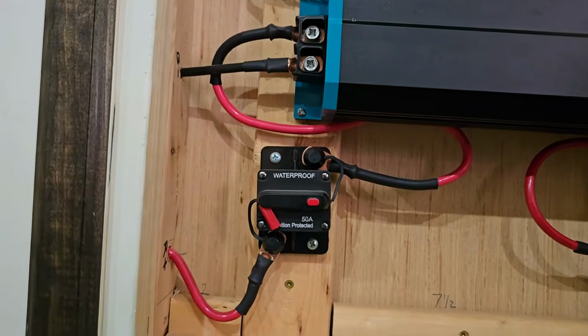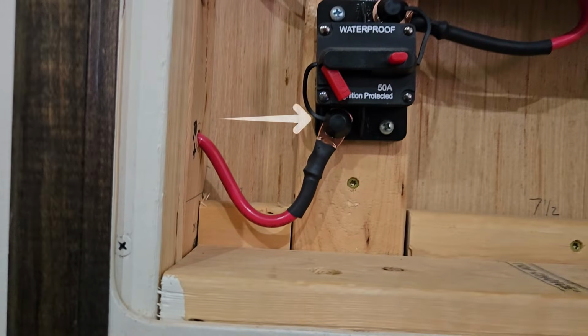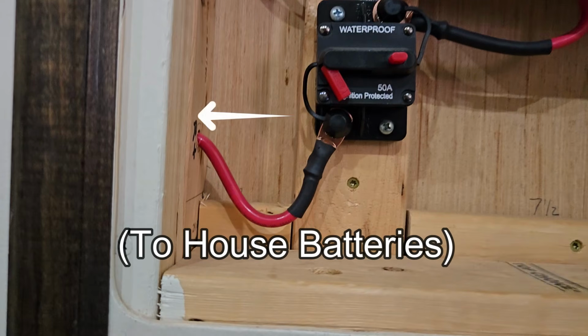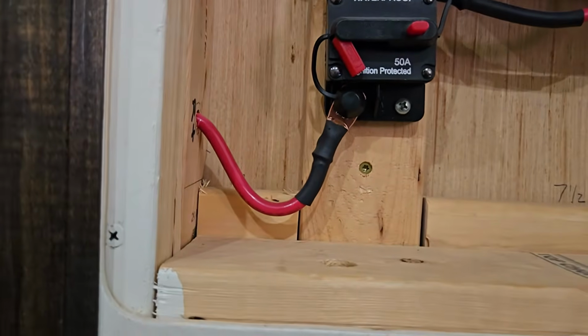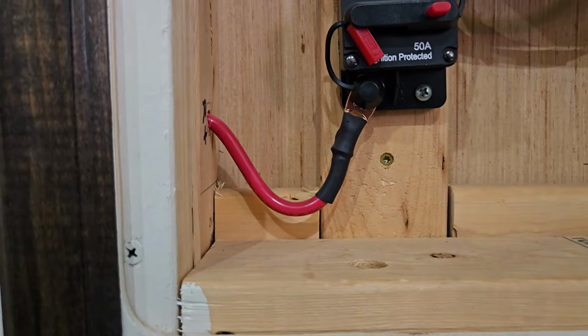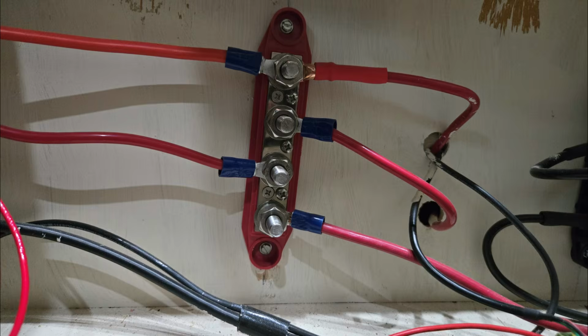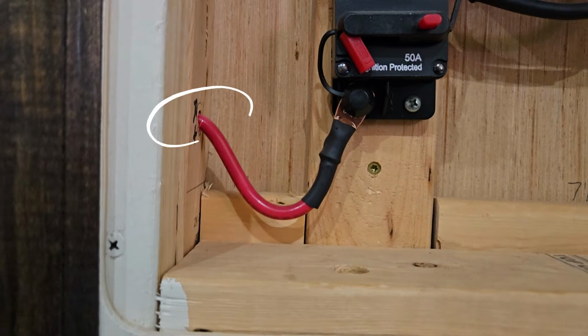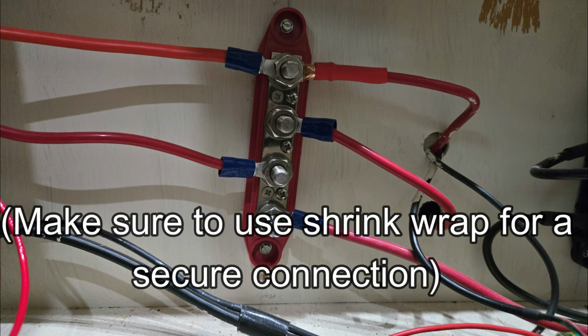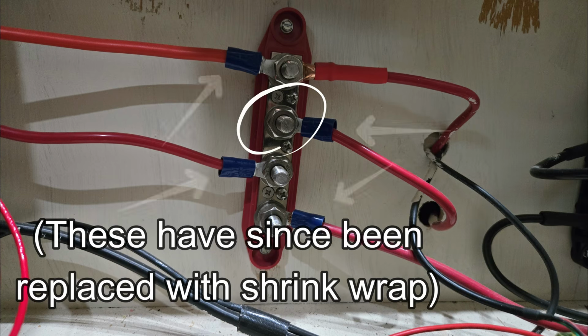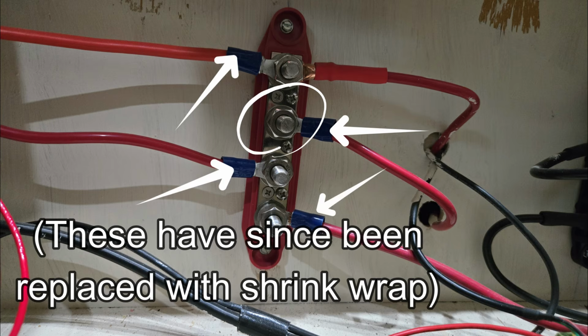Next, we'll attach a positive wire to the aux side of the 50 amp circuit breaker. As before, strip the wire and attach a lug, then attach the lug to the circuit breaker. The final step for the positive wire is to run it from the aux side of the circuit breaker to your positive bus bar. To do this, snake the wire behind your walls until it reaches the bus bar. Cut the wire, strip it back, and attach a lug. Then, attach that lug to an open terminal on your positive bus bar and use a washer and nut to secure the lug to the bus bar.